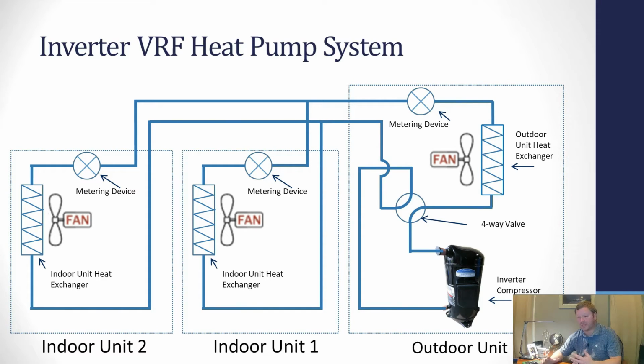Now, to give you an example, when you get to that 2 zone or the 3 zone or 4 zones, VRFs can, depending on brand, have up to 10 indoor units in some cases, all on one heat pump. We're just looking at a very basic layout here. When you go to a VRF system, you no longer have a handheld controller. You are adding a thermostat of some kind, a hardwired remote controller that can sense room temperature at the controller. So we're not using the return air like we do on mini splits. So that 3.5 degree offset goes away.